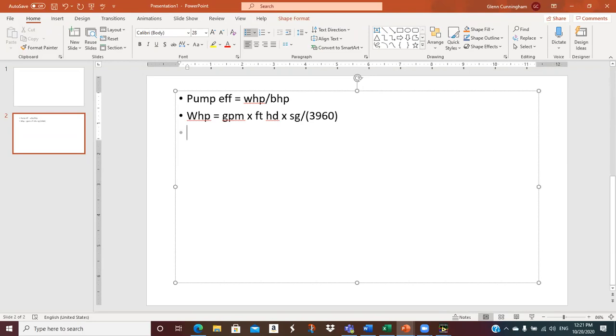Okay. So we got a certain GPM through the pump. It picks up a certain feet of head going through the pump. And then if the specific gravity is other than 1, we multiply by that. And then we divide by 3960. So that's the water horsepower.